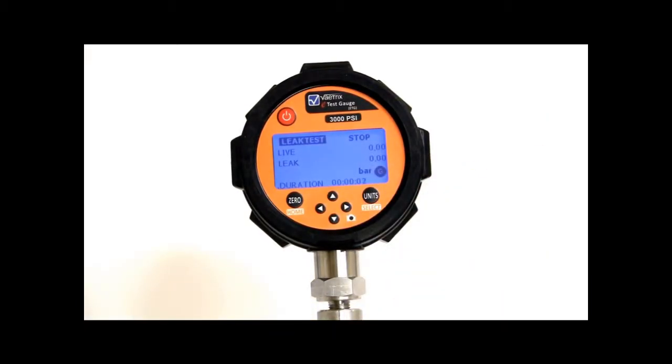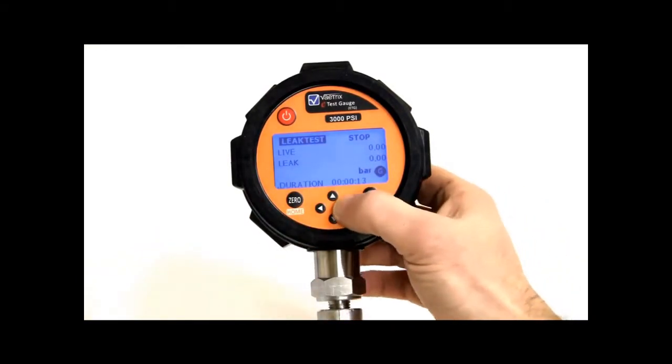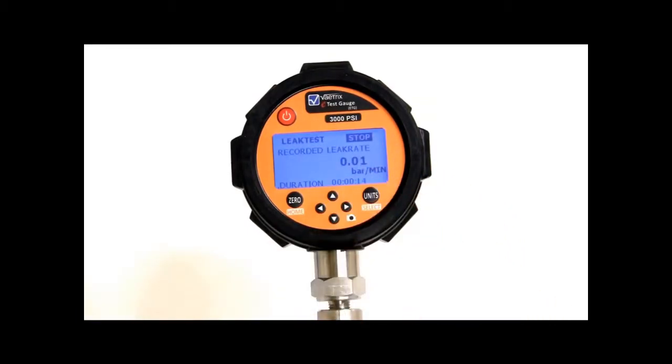So now I'm in live leak test mode. So leak test lets me check cylinders, tanks, anything that you want to check for a leak. You have to run for 10 seconds and it will tell you the leak rate. So I can scroll over, hit stop. It's going to tell me the leak rate in whatever units I'm in per minute.